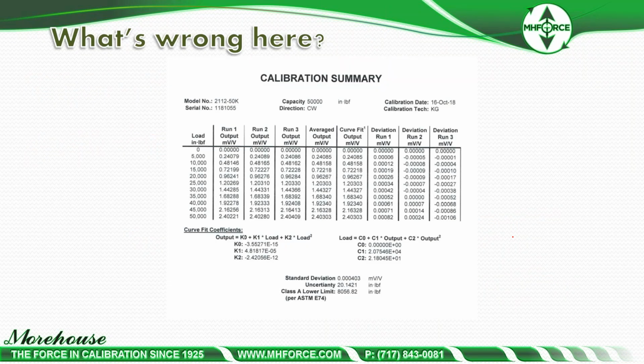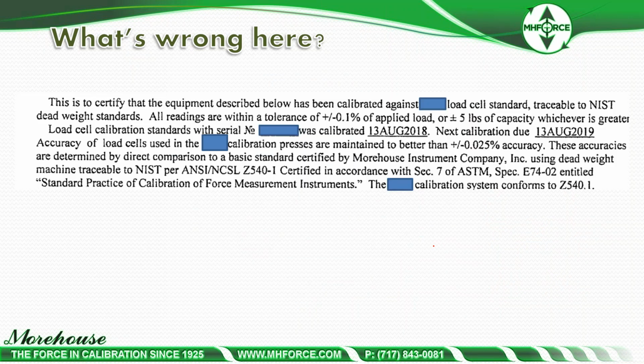If we look here, more examples of scopes you find on what's wrong. This is really interesting. Not only are they referencing torque in the wrong units, torque is absolutely force times length, right, people? No one ever says meter Newton. It's Newton meter, so it should be pound inch. Not only are they mentioning that wrong, but here's an example where they're referencing ASTM E74. This is not the standard for torque. There's clockwise here. Nowhere near the standard for torque. Torque is ASTM E2428. So wrong standard completely. Someone got away with this. It's a shame. Then here's another one.